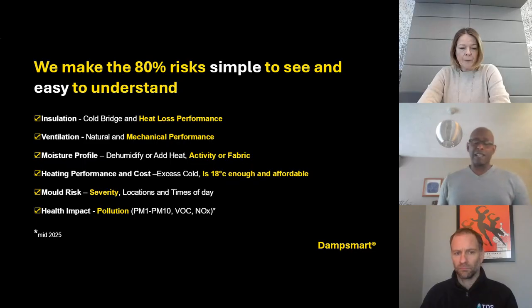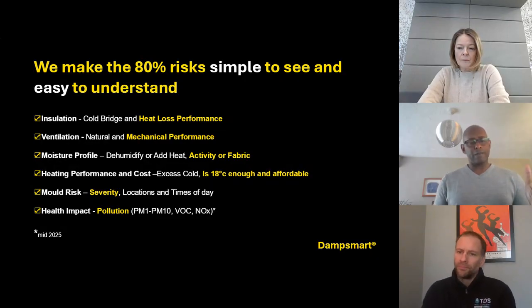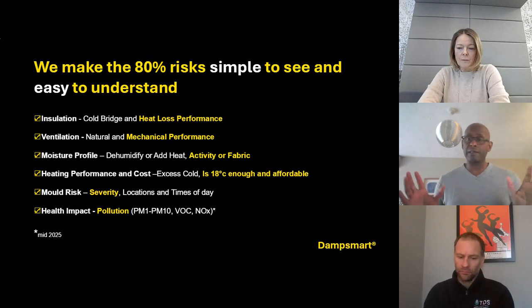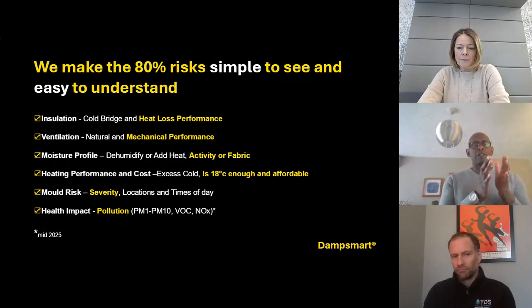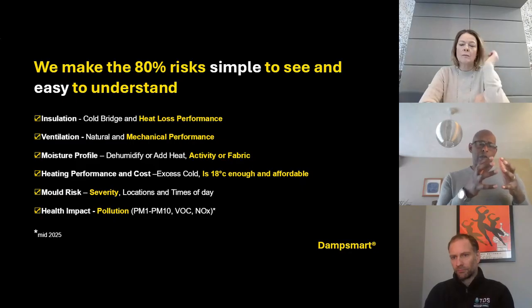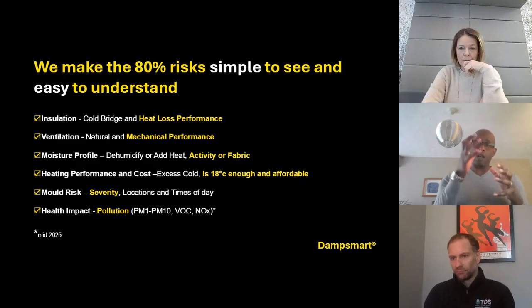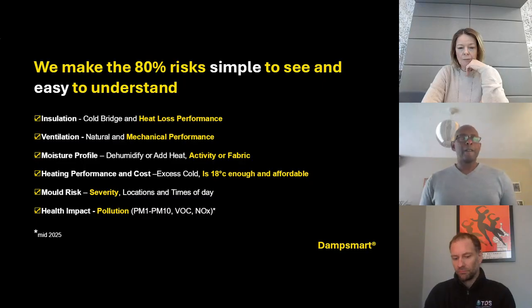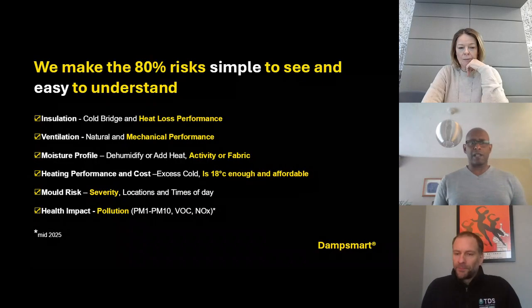And the heating performance, that's a really important thing, because too often we've seen inspectors go around to a property and say, yeah, it was nice and toasty warm, it was great. But actually, that was on that day. And not only was it toasty warm for just a couple of hours on that day, when we then look at the data, we can see when that heating does go up, whether it does go up enough, and whether it stays on for long enough as well to prevent the moisture from condensing.